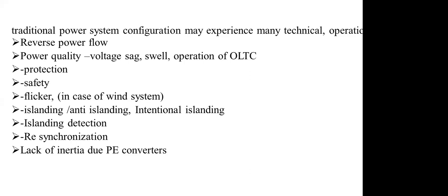If there is a lot of disturbance in the grid, it may be detected as a grid failure. At that time your distribution or renewable source will disconnect from the grid, and then it will try to reconnect. At that time also you will get a lot of power quality issues.